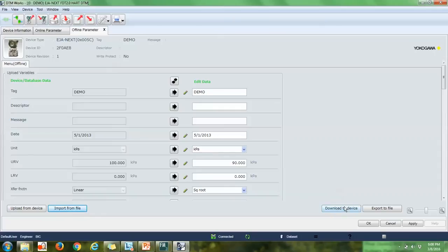So we'll go ahead and download this to the device and change that span. It takes a little bit longer because every parameter is being adjusted, unlike in the online menu, where it was point by point and a little bit quicker. Now we can see in the menu that it's been changed to 90 kilopascals. So that file did take.